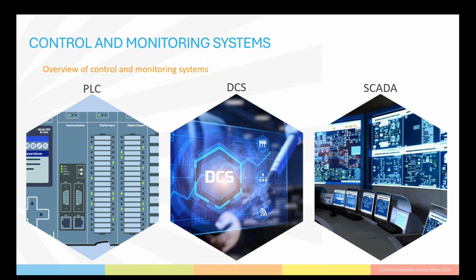From a layout perspective, DCS typically requires a set of stations to control everything in the plant. PLC-based systems give control local to the equipment or systems in the plant, as well as control within the DCS. Vital systems may need to have their own station in the control room. Fire safety, for example, is a separate station, and it must remain separate from the plant control system. SCADA is the software that shows graphically what's happening in the plant and runs on the DCS. That station could be either in the control room or remotely operated. Other considerations are console design, screen layout, alarm management, networking and connectivity, redundancy, and backup. The placement of operator stations, consoles, displays, and other equipment influence the overall size, layout, and design of the control room.